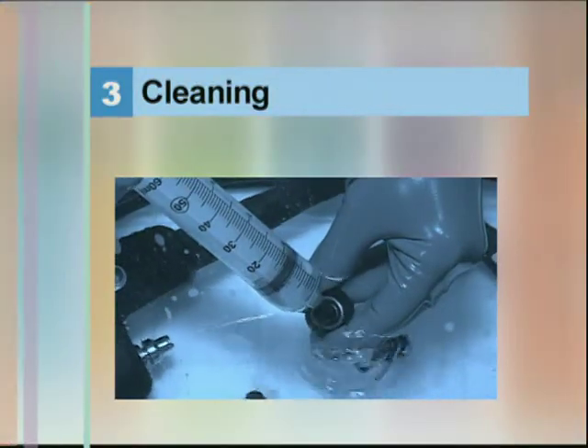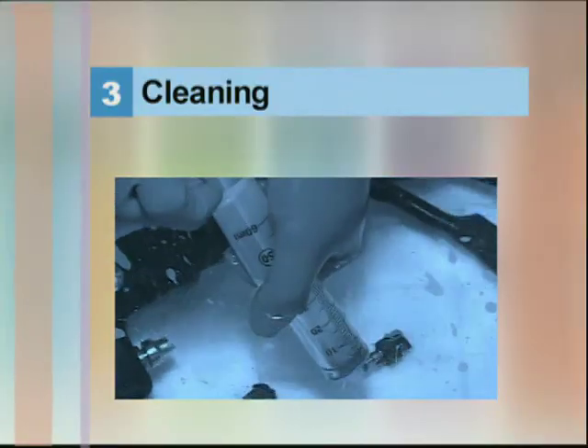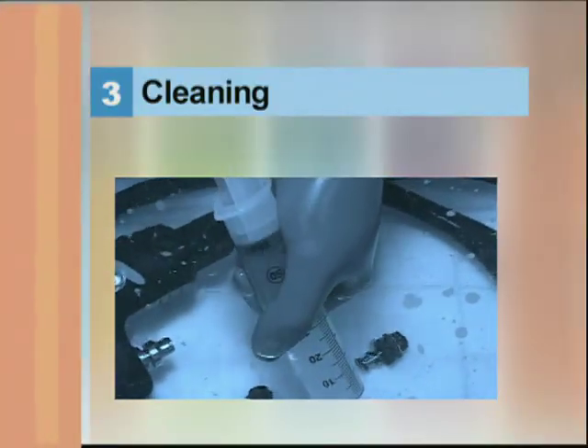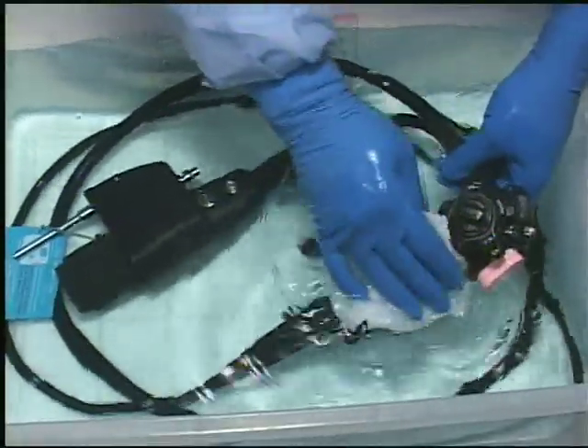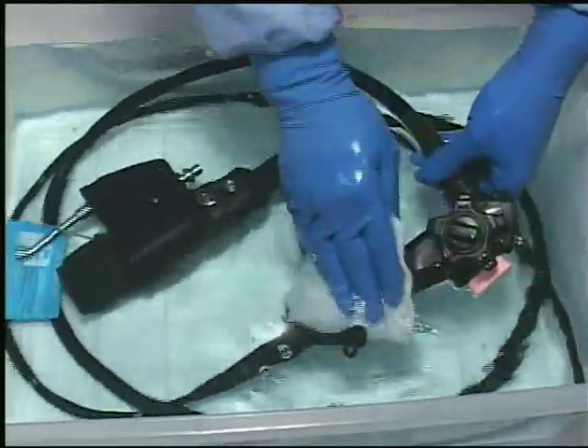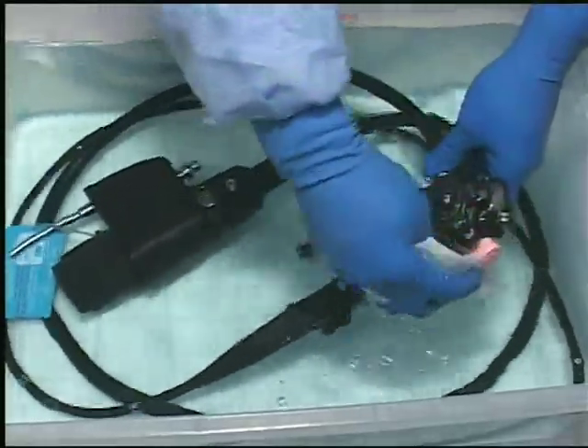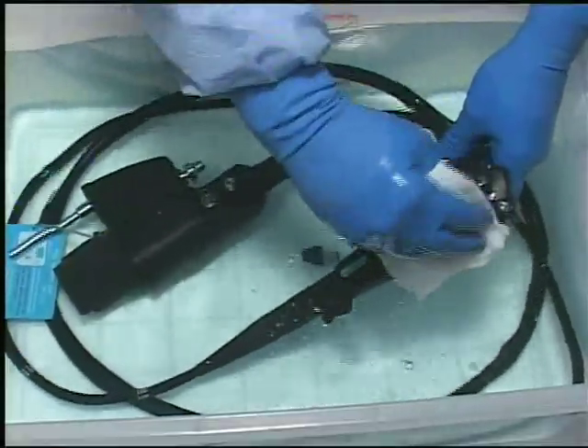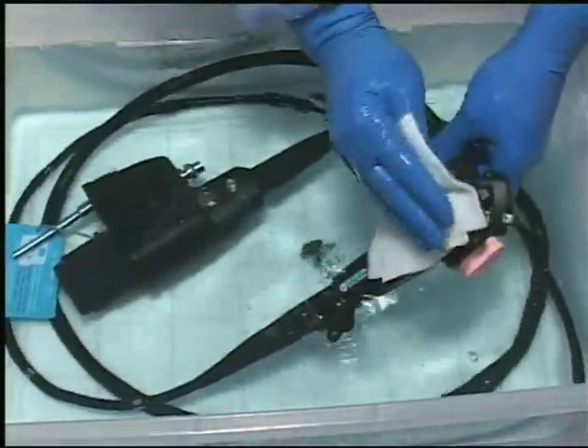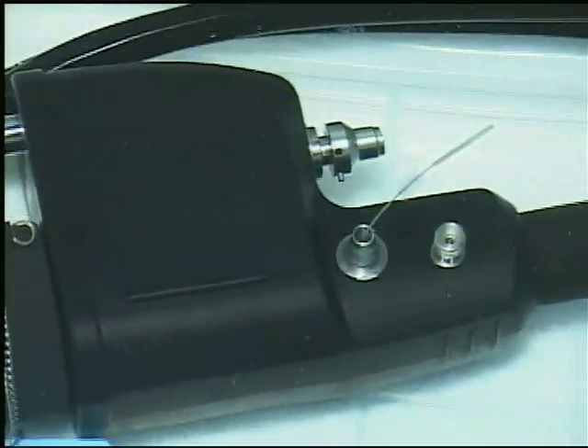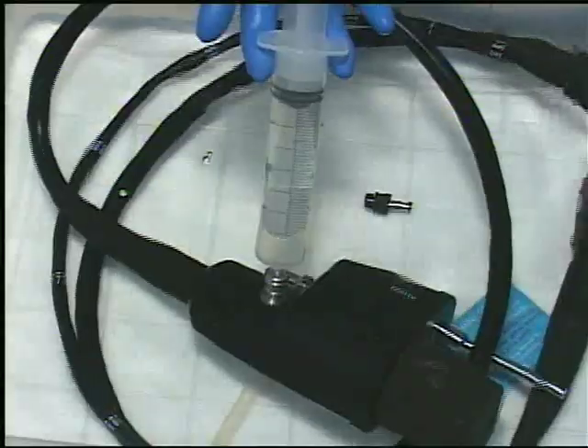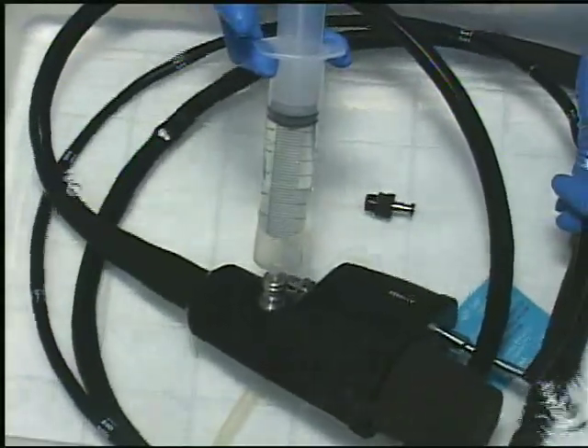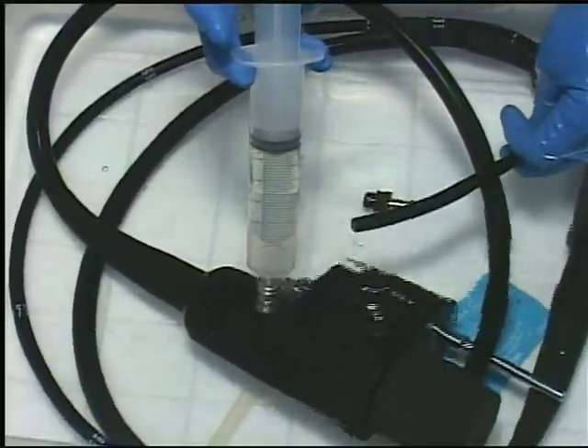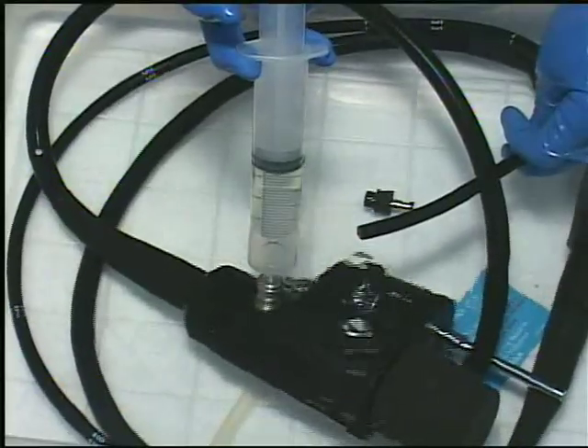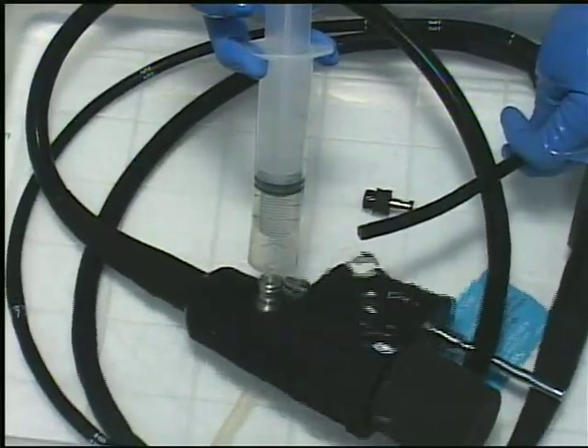Cleaning should be performed in a decontamination area prior to any subsequent disinfection or sterilization process. Cleaning goals: to lower or minimize the number of pathogenic organisms remaining on the endoscope, to reduce or remove the amount of patient debris, blood, mucus, etc., which may be left on the endoscope, within its channels, and/or on removable scope components. Cleaning is always followed by a water rinse step to remove residual detergent and debris and to prevent dilution and/or adulteration of the disinfectant.